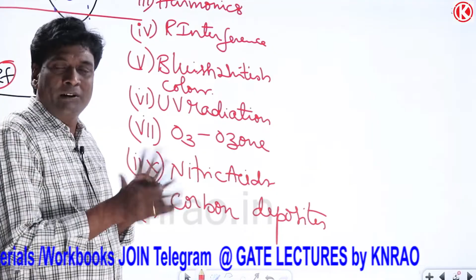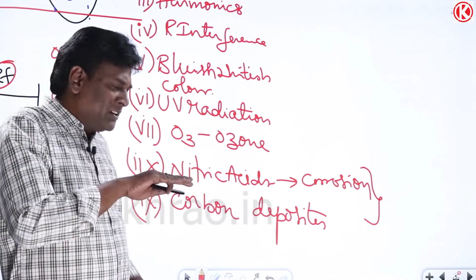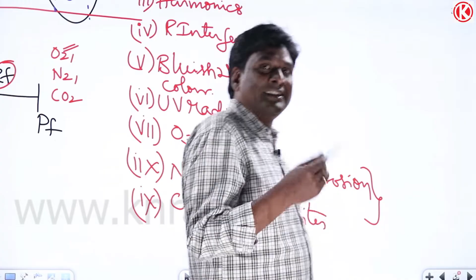Because of nitric acids, a kind of corrosion effect will be there on top of the conductor, because acid causes corrosion, right? So corrosion effects will be there. And because of these two, you can observe some kind of white powder. At starting, during installation, you will not have any white powder around the conductor, but after some time, because of corona, white powder deposits will be there because of salts or whatever it may be.